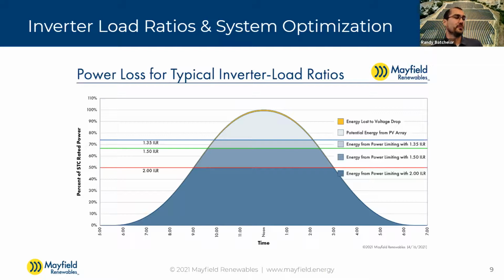But yeah, a lot of scenarios we are seeing people with these really high loading ratios, and the general rule of thumb, pretty much across the board with all different types of inverters, you're getting general feedback that 1.5 is sort of a limit on inverters, and that's still kind of a reality. But what we're also starting to see is that, because across the markets and across the industry there is a push for higher loading ratios, the inverter manufacturers are getting much more sophisticated in how they talk about this topic.